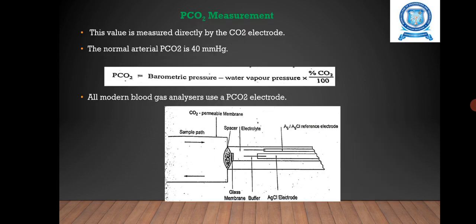PCO2 measurement. This value is measured directly by the CO2 electrode. The normal arterial PCO2 is 40 mmHg. It can be expressed as PCO2 = (barometric pressure - water vapor pressure) × (%CO2/100). All blood gas analyzers use a PCO2 electrode.